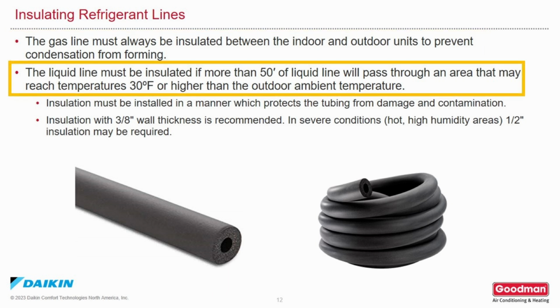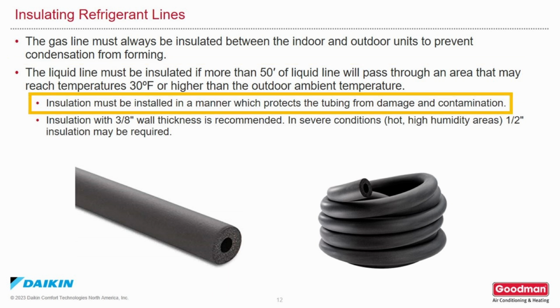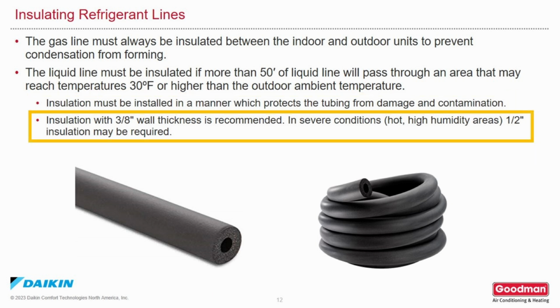If the line set passes through an area more than 50 feet long that would reach temperatures 30 degrees Fahrenheit or more above outside ambient temperature, then the liquid line should also be insulated. Install the insulation in a way that it will protect the tubing from damage and contamination. 3/8-inch wall insulation is recommended, but if you are in severe conditions, very hot or humid areas, then you may need to go to 1/2-inch insulation.